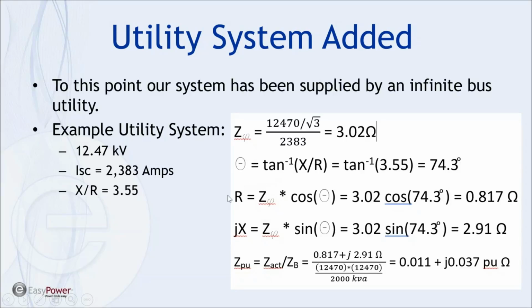And then again, thinking in terms of a right triangle, the resistance in ohms is the magnitude of the impedance Z times the cosine of theta. That gives us 0.817. I did these kind of quickly. Sometimes I get sines and cosines backwards, so hopefully I didn't do that here. And then jX is the sine of the angle times the impedance, and that gives us 2.91. So the system then, in terms of ohms, looks like a series impedance of 0.817 ohms resistance and a 2.91 inductive reactance. Then I call that the actual impedance, we have to convert that to per unit.